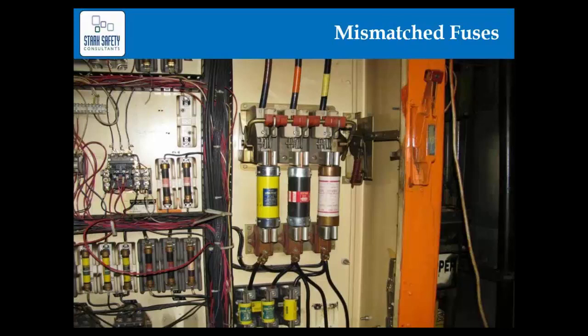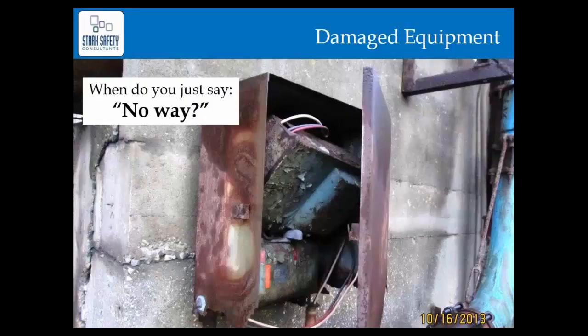Deciding upfront how you'll tackle mismatched fuse problems is most advantageous. Eventually you may find equipment in such bad condition that it's not responsible to evaluate it at all, other than showing there's no protection and trying to get it corrected before finishing your model. Putting a label on equipment like this is almost ludicrous, so sooner or later you may have to exclude it from your analysis and simply note that it needs to be corrected.